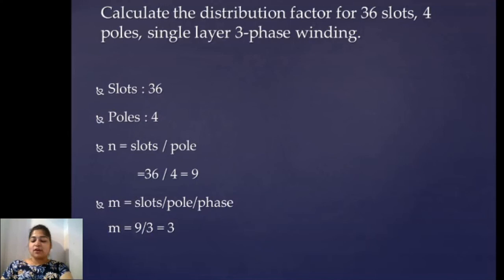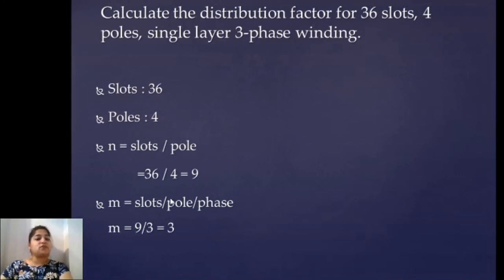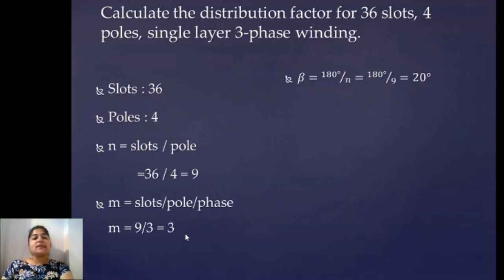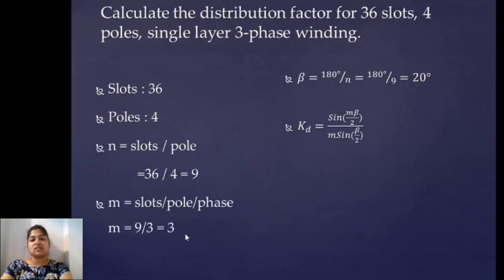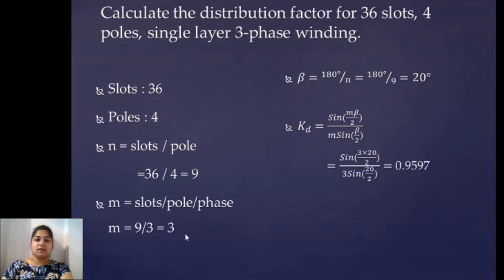Next, we calculate m — slots per pole per phase. Slots per pole is already 9, so we divide by the number of phases. Since it is 3-phase, dividing by 3 gives m as 3. Then we calculate beta: beta equals 180 divided by N, and N is 9, so beta equals 20 degrees. With m and beta known, substituting into the distribution factor equation kd equals sine(m·beta/2) divided by m·sine(beta/2), we get kd equals 0.9597.